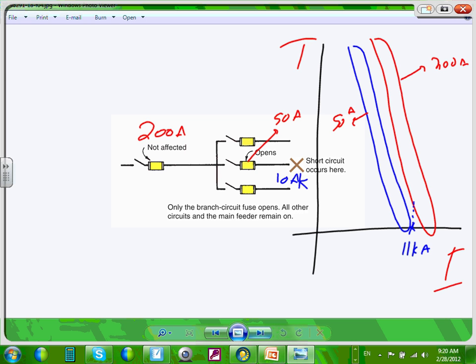So the short circuit here is actually, say, 10,000 amp. Up to 10,000 amp, this guy is taking care of it, and we are guaranteed that this will never go higher than 10,000 amp. If it goes higher than 10,000 amp, then we're in this area, a short circuit right in this area, right? And you need which one to trip? The main to trip. Any questions, guys, about a fully coordinated system? What you are looking at is fully coordinated fuses. Please remember the graphics, because that's what PTW is later going to be talking about, a fully coordinated system.